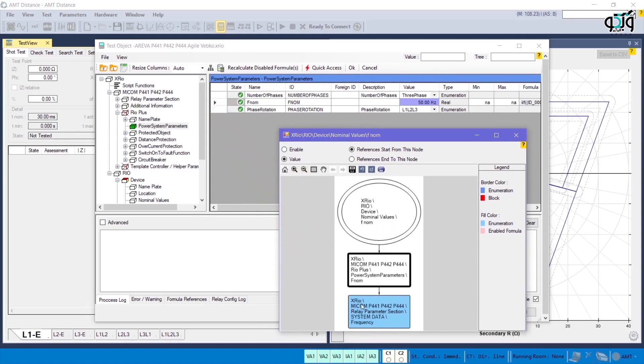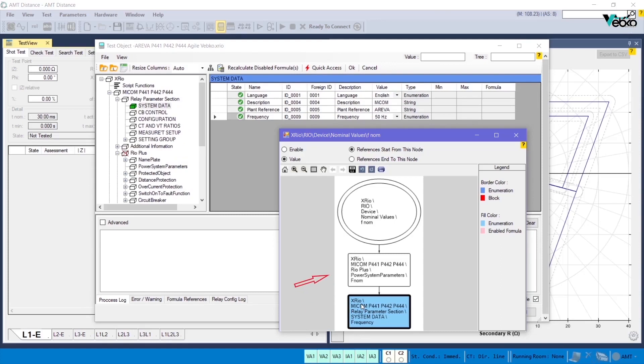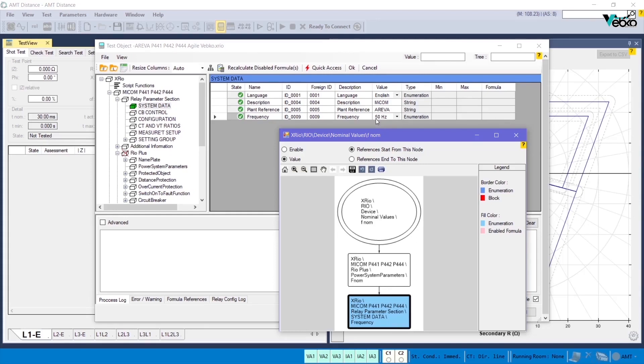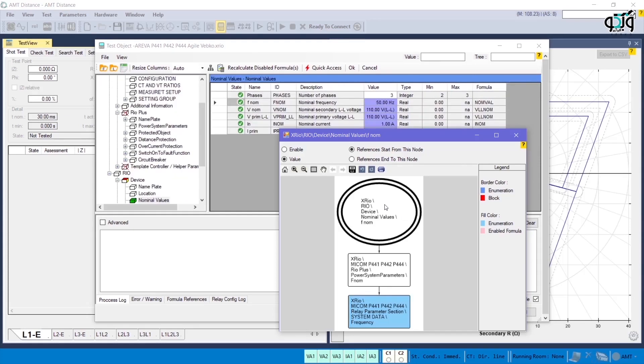The value of FNOM parameter is itself based on a formula and is dependent on another parameter, which by clicking on the map box you can see that a parameter named frequency is used. This means that, since 50 is set as the value for nominal values, the value for FNOM according to its formula is 50, and finally the amount of nominal frequency in nominal values, according to the defined relation, is 50 Hz.